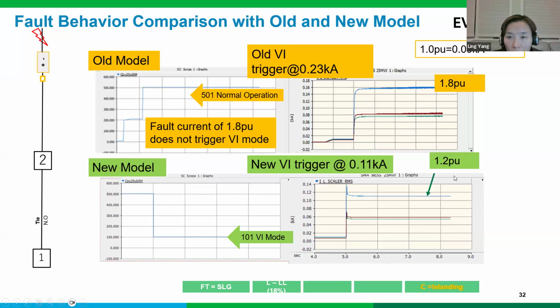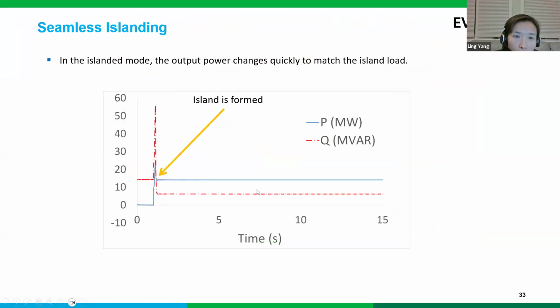for currents. By reducing the current contributed from the inverters, we were able to reduce the transient overcurrents under this circumstance. This is just one of the scenarios where we form an island, and then the BESS is able to constantly produce P and Q, supporting the island.